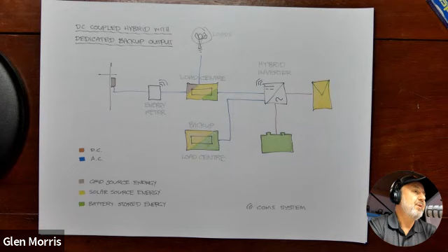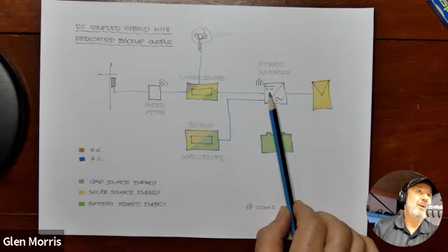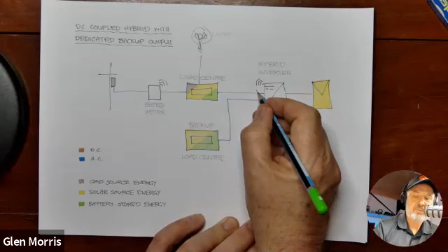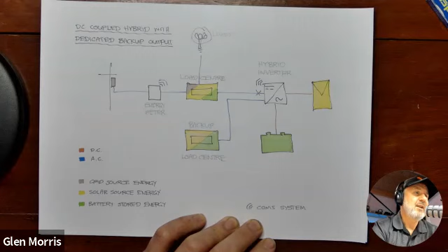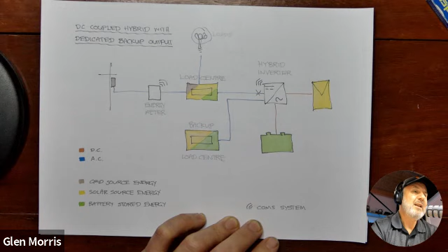A true UPS system has no break, but these systems have to have a switched break, but it's done very quickly, often 10 milliseconds. So if the grid fails, this circuit here will have typically a half cycle interruption and then carry on working in standalone mode. And so the advantage there is almost no loss of power. Now, for many appliances like lights, even computers, often they won't even notice that half a cycle loss of power, but some sensitive equipment may reboot.